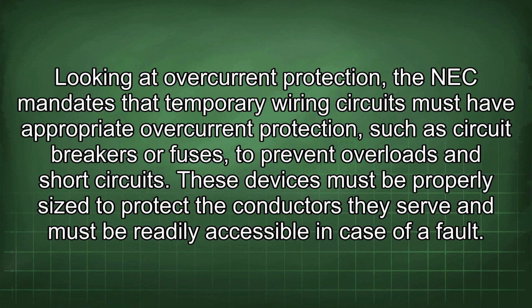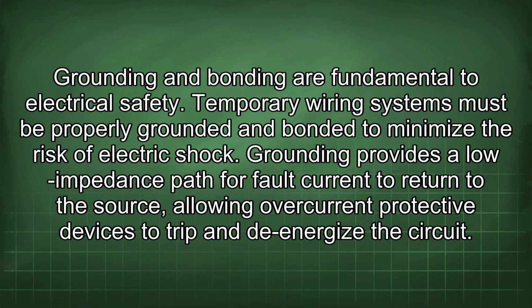Looking at overcurrent protection, the NEC mandates that temporary wiring circuits must have appropriate overcurrent protection, such as circuit breakers or fuses, to prevent overloads and short circuits. These devices must be properly sized to protect the conductors they serve and must be readily accessible in case of a fault. Grounding and bonding are fundamental to electrical safety. Temporary wiring systems must be properly grounded and bonded to minimize the risk of electric shock.